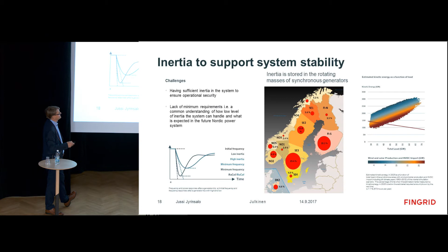But the end result is that in 2025, it seems that some 8% of the hours of the year, the system cannot anymore tolerate the tripping of the largest unit. So there is quite a big probability for the system having too little inertia. Something needs to be done for this.